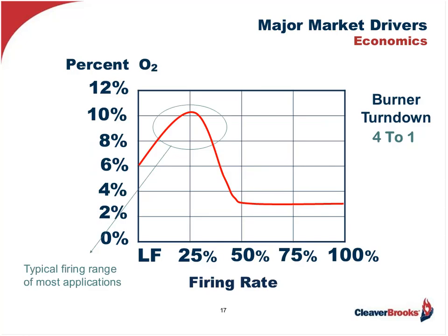You see where many of the burners operate today because the burner-boiler combination was not properly sized to the load at the outset, or the fuel-air ratio was not adequately controlled at the lower firing rates due to wear and poor damper blade design. Notice how the excess air climbs once dropping to the 50% firing rate. Substantial dollars are wasted here, and in most cases, people are just totally unaware.